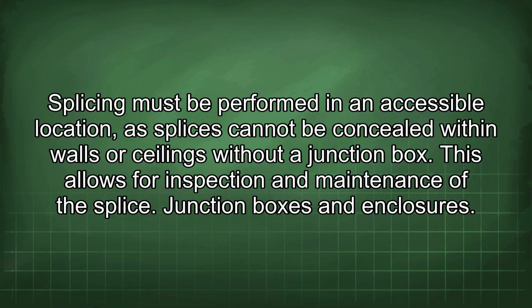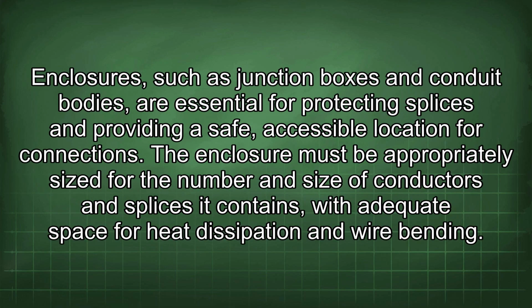Junction boxes and enclosures. Enclosures such as junction boxes and conduit bodies are essential for protecting splices and providing a safe, accessible location for connections. The enclosure must be appropriately sized for the number and size of conductors and splices it contains, with adequate space for heat dissipation and wire bending.